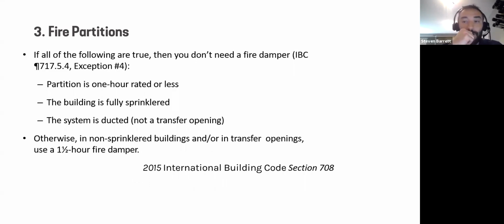And just like the other two, the baseline requirement is to provide a fire damper. The exception for fire partitions is a little more lenient. It's similar to fire barriers where 1 hour or less, which it's pretty rare to have a fire partition that's more than 1 hour, a fully sprinklered building and a ducted, not air transfer opening, and then you can omit the fire damper. Otherwise, if you do have a non-sprinklered building or you have an air transfer opening versus a ducted penetration, then provide a 90-minute or 1 1/2 hour fire damper.